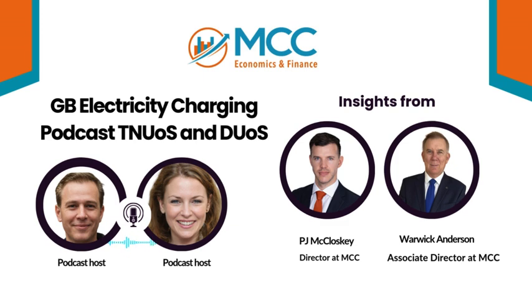What else? There's a capacity charge, which is based on the maximum amount of electricity that you might need from the network. Higher voltage connections usually have higher capacity charges. And then there's an exceeded capacity charge. What's that? It's a penalty if you underestimate how much capacity you need. Oh, so it's like going over my data limit on my phone and then getting hit with a fee.